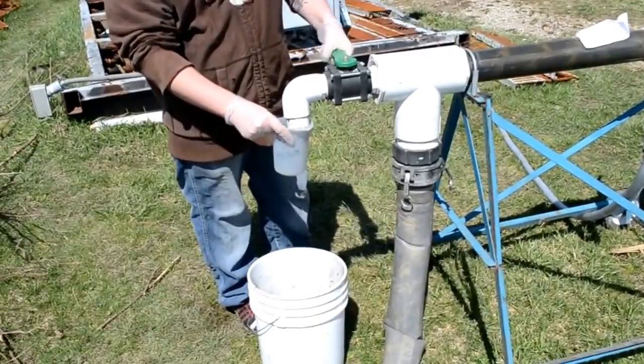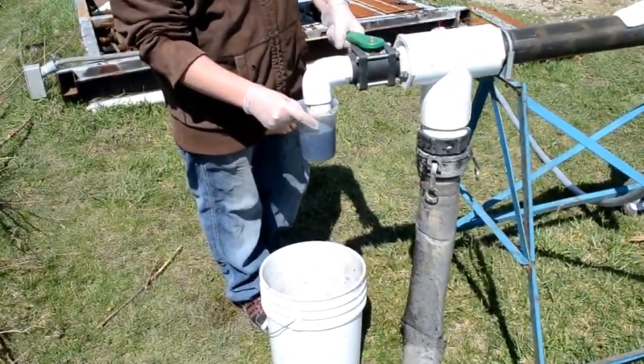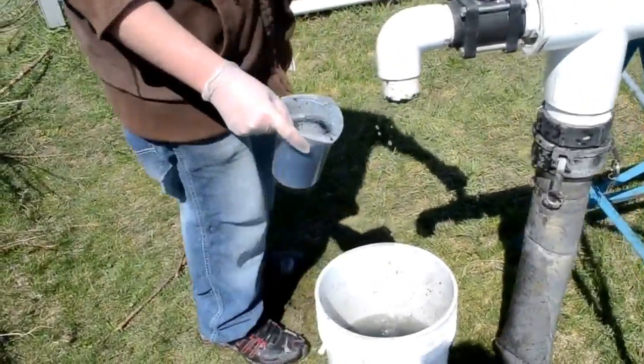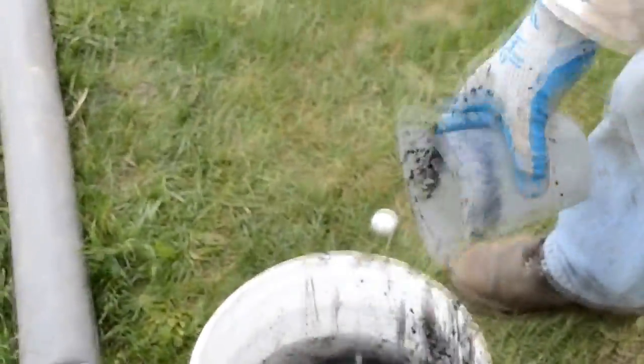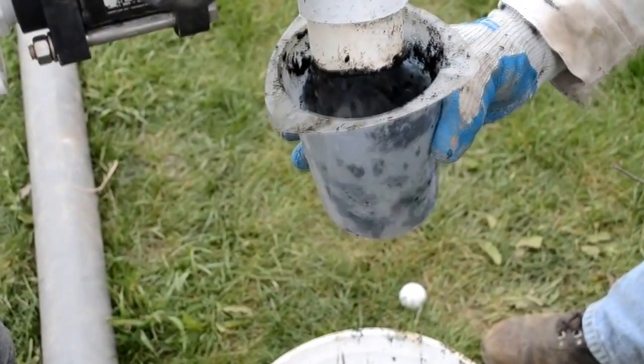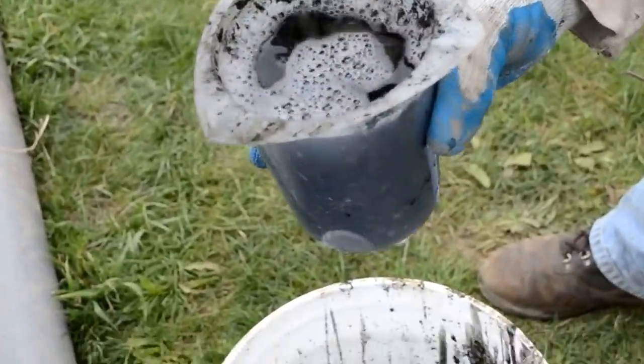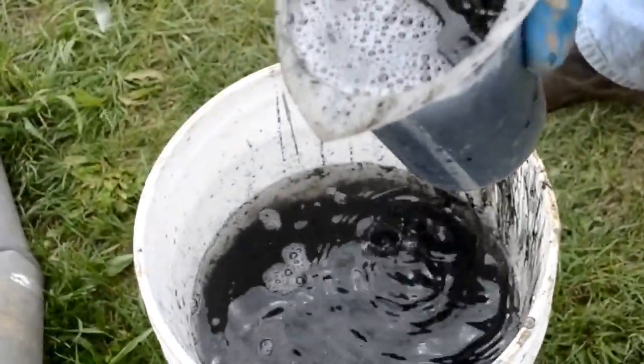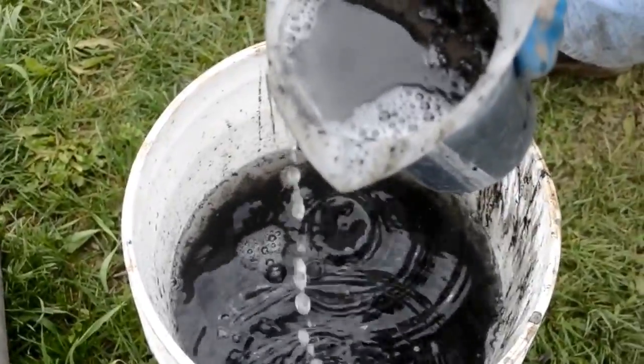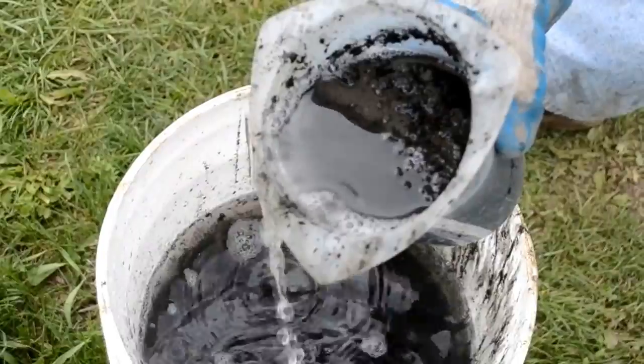The operator periodically checks the flock sludge to make sure everything is working as it should. If the correct flocculant and dosage is selected and used, the solids will form tight agglomerations and the clear water will be forced out. The clean water flows from the dewatering bag while the solids are trapped inside. Selecting the correct chemical program and controlling the process ensures that the dewatering operation will work as intended.